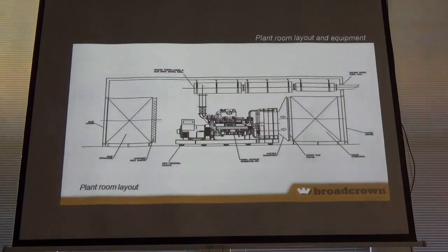Another case that I've seen, which is really unfair for us engineers, is that a data centre in London was there first. The chillers are on the roof. They have a dBA design for the design load at the time of the noise levels. They then go and build apartment blocks next to the data centre, the top floors overlooking the chillers. During the summer, when they've got the windows open, they've got the blooming noise. They then complain to the data centre company about the noise. They were there first, and then the data centre company's got to pay for attenuated screens. That's like building around an airport and complaining about the noise, isn't it? Yeah, but it's just unfair, really.